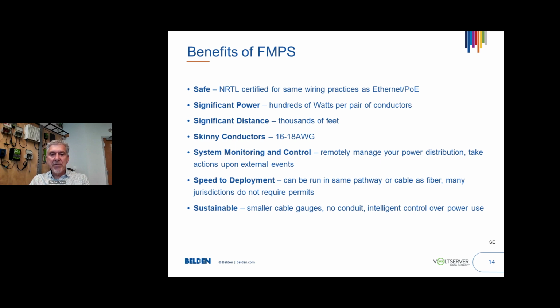You can run digital electricity extremely easily. If you have experience of having traditional conduit-based power installed versus an IT installation, say of Ethernet or USB cable, that'll give you an idea of the difference in speed and ease in terms of deployment. And it uses a lot less material, in terms of ESG and sustainability benefits. Because, as we mentioned, you're distributing an inherently safe form of electricity, you don't need all those things after the power source to protect people and buildings from it. So the easiest way to look at it is just by eliminating hard conduit runs. In a typical building, you're removing thousands of pounds of carbon-intensive steel or aluminum. So that's one of the other benefits of fault-managed power.